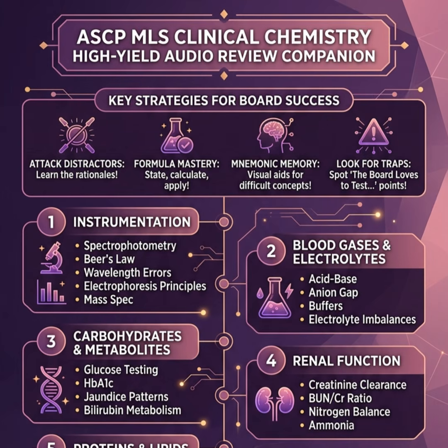Wait, yeah, why wouldn't it ruin a low concentration sample just as much? It comes down to percentages and the concept of signal-to-noise ratio. Imagine a highly concentrated patient sample. It's a very dark solution. Because the concentration is so high, the absorption is immense, meaning the actual transmitted light successfully reaching the detector is at its absolute lowest. Right, so let's say only 1% of the original light is supposed to make it through. If your machine has a tiny leak and 2% stray light sneaks around the cuvette and hits the detector, your detector now registers 3% total light.